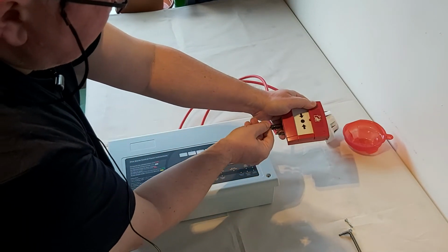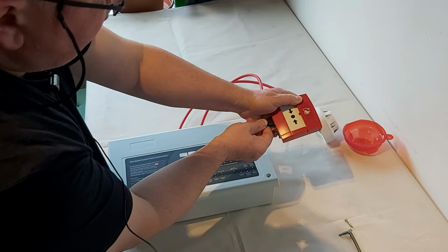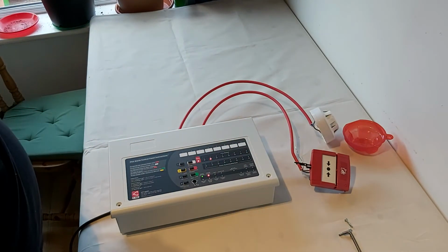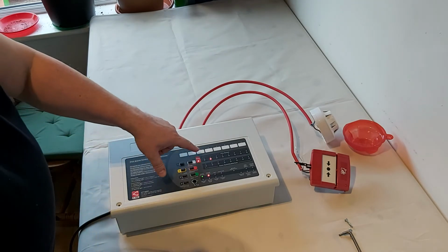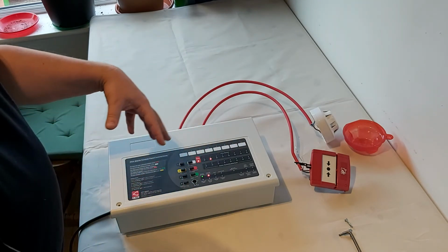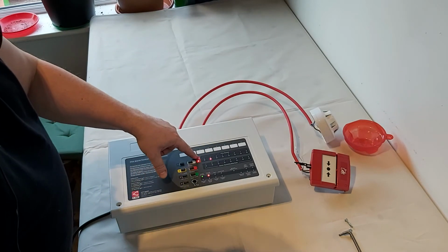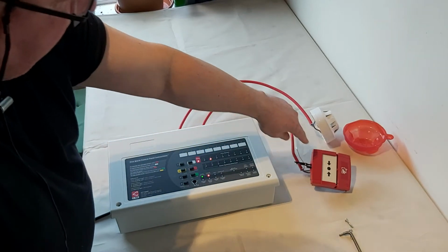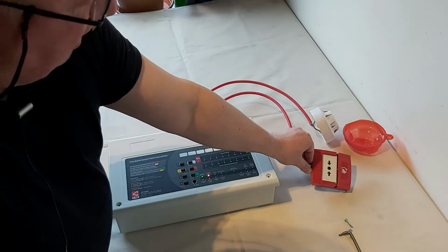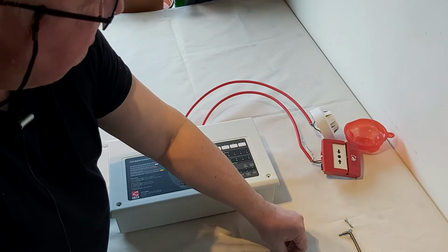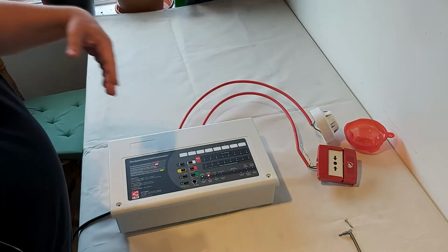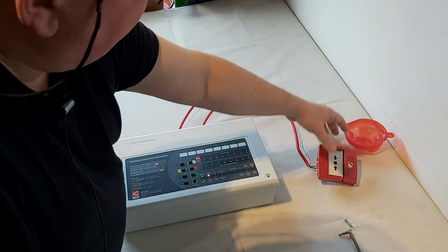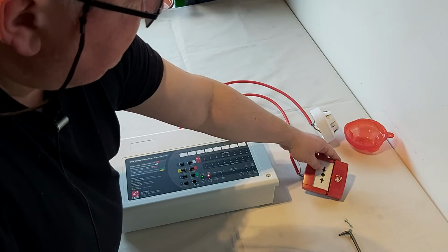We won't be pressing that. Okay. And you can see we have a fire. So there's no orange, yellow LEDs, there are red LEDs. There's a general fire and fire on zone 2, because zone 2 is that break glass. Now we cannot reset the fire alarm until the fire condition on the detector zone is removed. So either there's no fire or break glasses are all reset.